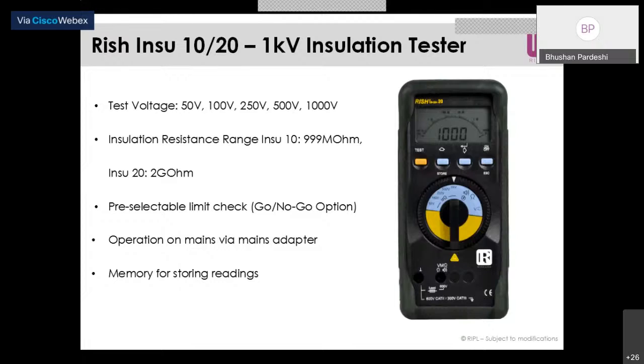Now, one more point I need to add: we should always know why insulation mostly gets degraded in the system. Mainly there is electrical stress, like surges or voltage spikes in any device; mechanical stress, like vibration, movement or impact; chemical attacks, like dirt, oil, corrosion, rain, vapors; thermal stress, like cold or hot conditions, or when we start and stop the machines; or environmental conditions like moisture and humidity. All these five things attack the insulation of any device, and if we do not maintain the insulation, that can lead to a failure of the device.